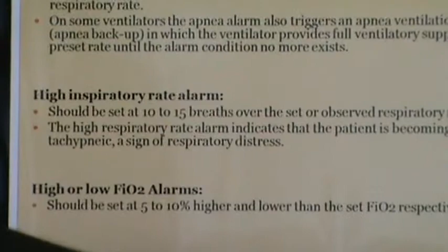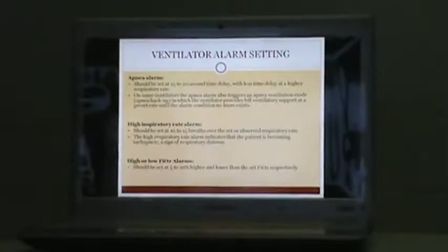High or low FiO2 alarm. This is 5 to 10 above and below the set FiO2. In that case, if there is a fall in the central O2 supply, you will get that alarm.